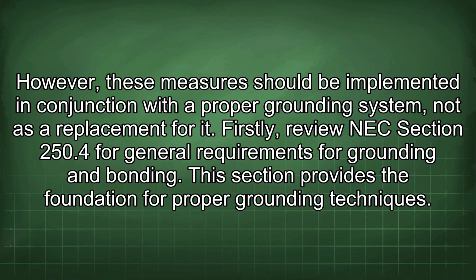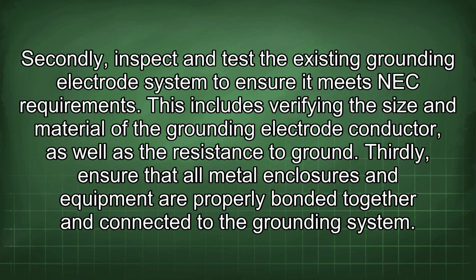Firstly, review NEC Section 250.4 for general requirements for grounding and bonding. This section provides the foundation for proper grounding techniques. Secondly, inspect and test the existing grounding electrode system to ensure it meets NEC requirements. This includes verifying the size and material of the grounding electrode conductor, as well as the resistance to ground.